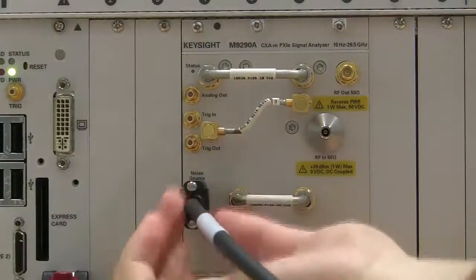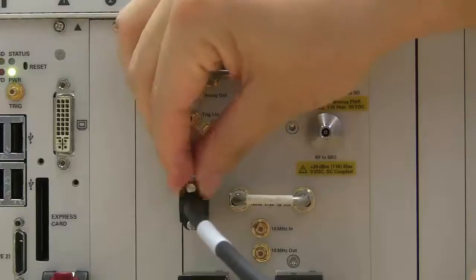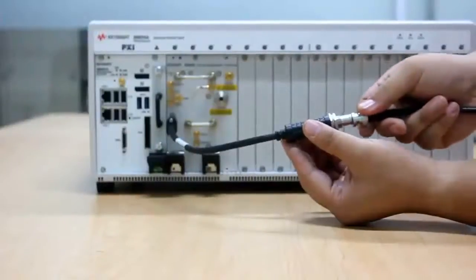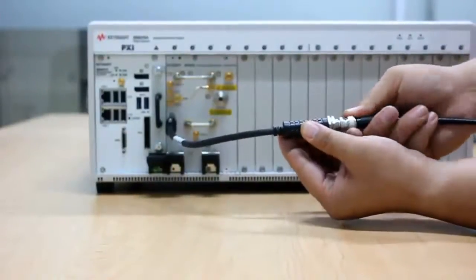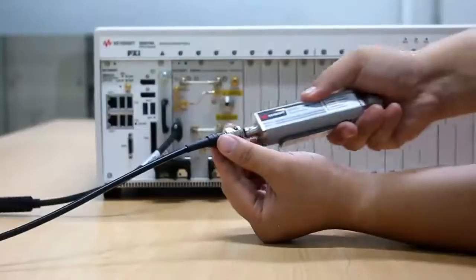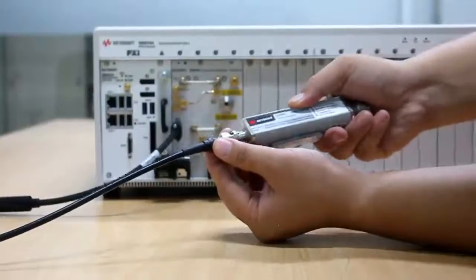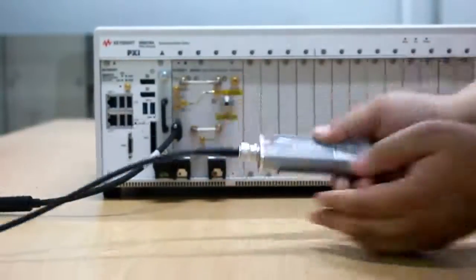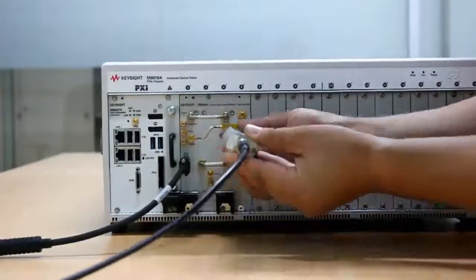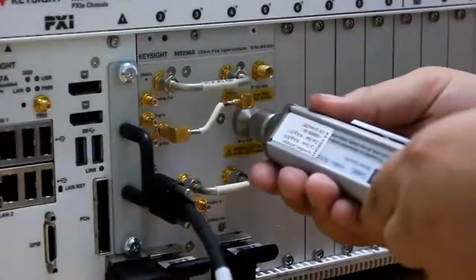Connect the noise source input to the CXA-m via Y1282A connecting cable, and connect the noise source output to the RF input of the CXA-m.